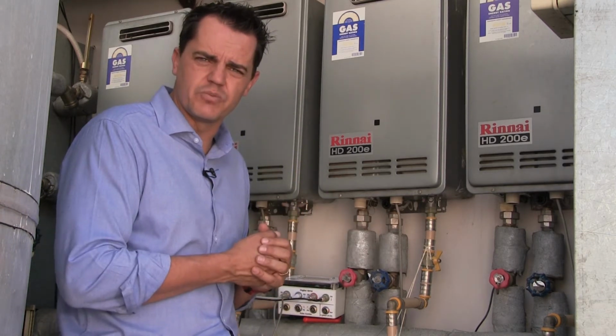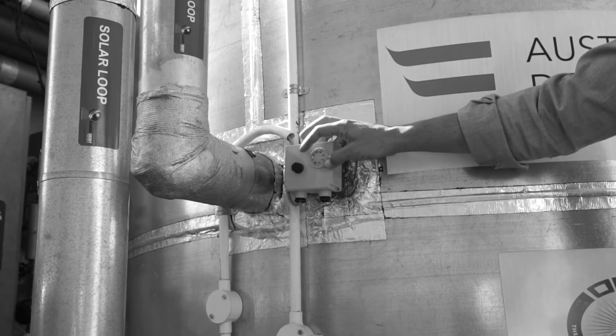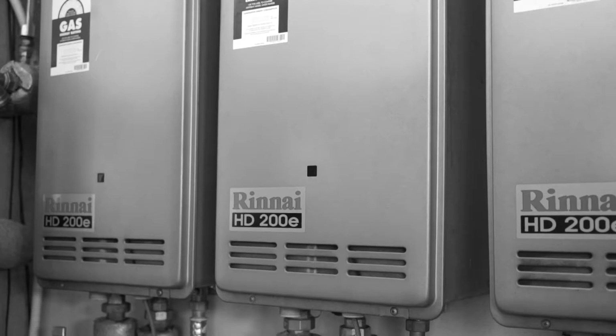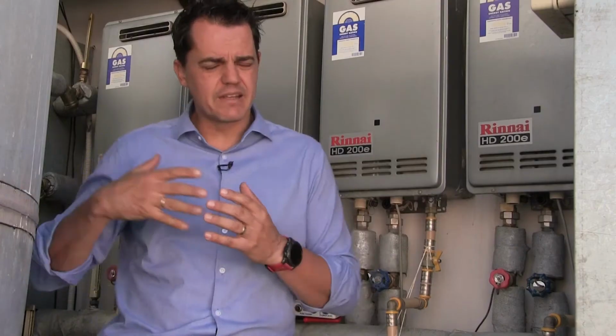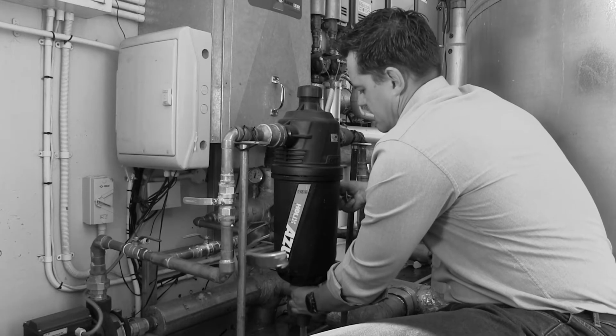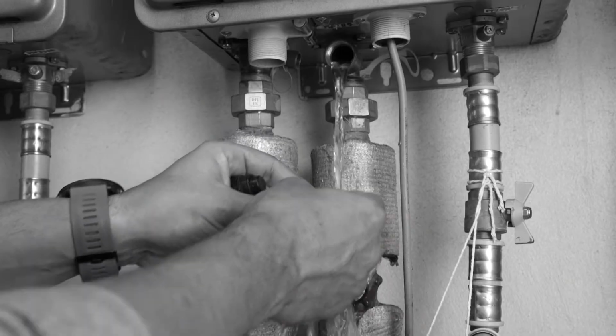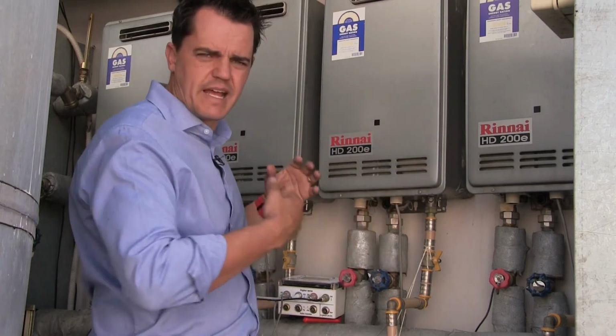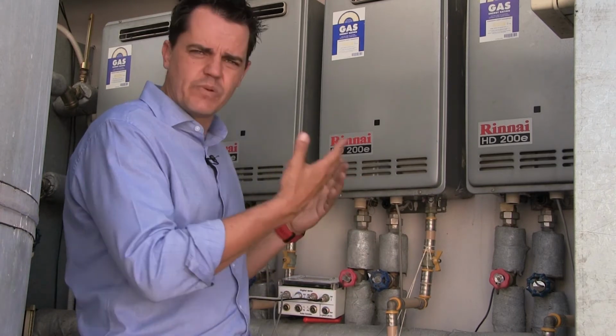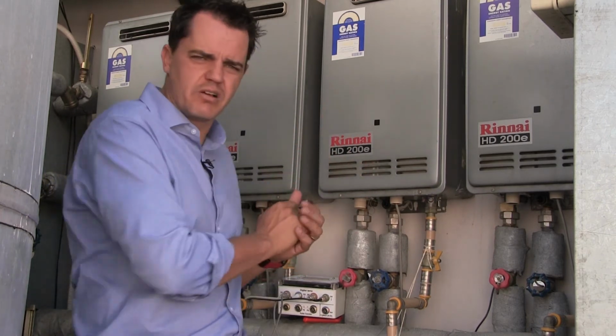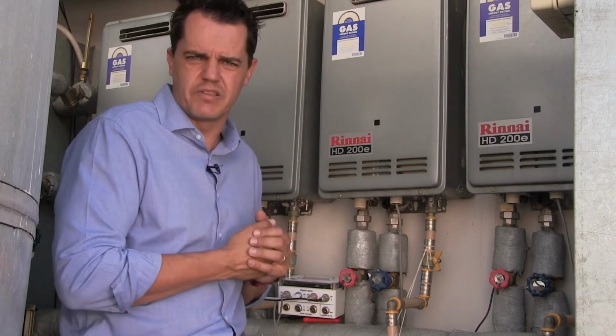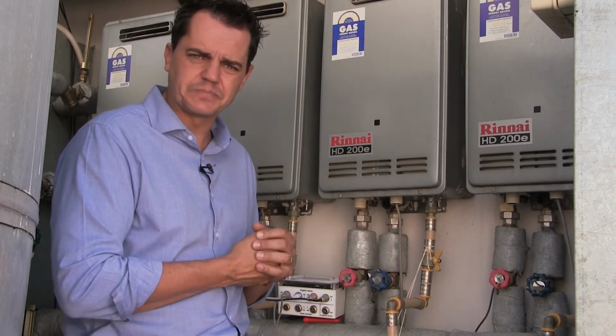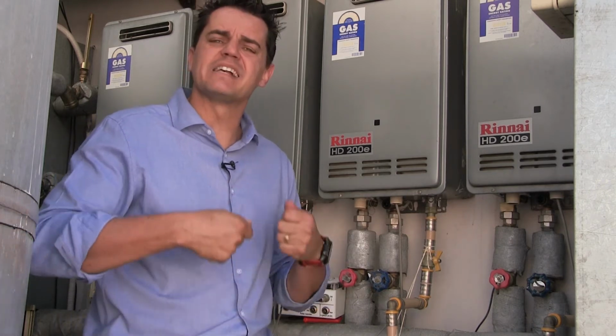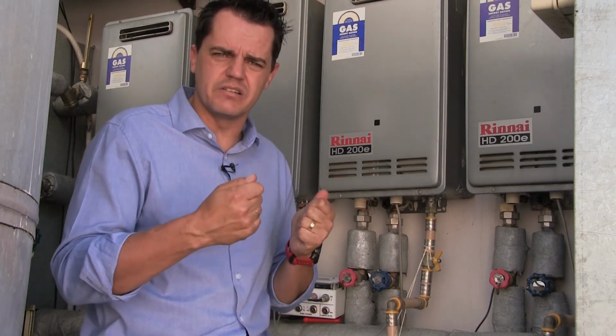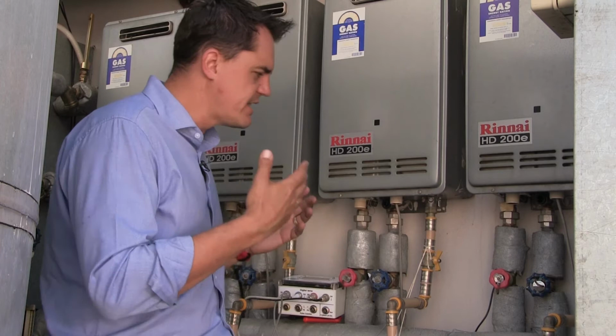So in the first videos, we've showed you the initial checks, where to do the fault finding and identify if there's a problem with the burners. The second video, we had the filtration system, where we showed you how to flush the main filter and the Rinnai filters. In this video, really you need to understand what the error codes are, and at least when you phone the contractor to say there's an error code 10, it refers to the venting of the unit, please come and fix it. What I have found is, as an interim measure, really just to give hot water to the students as an interim measure, it does help.